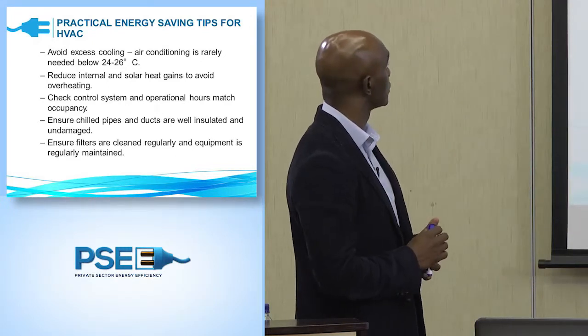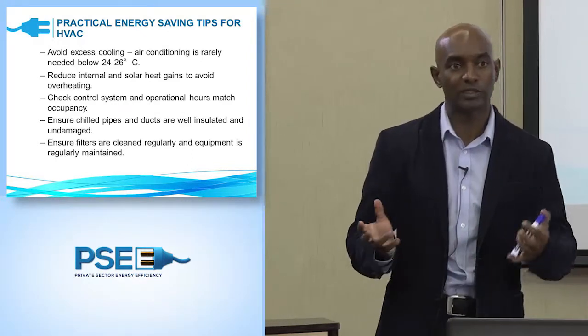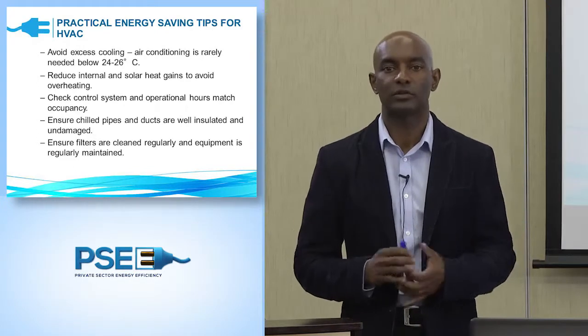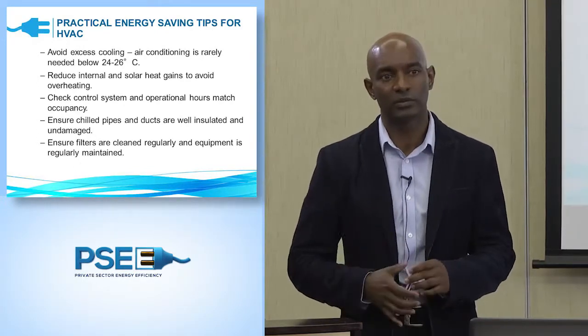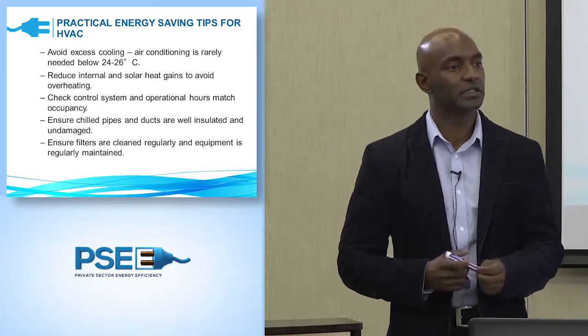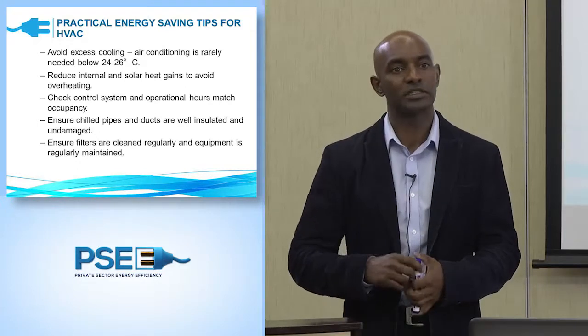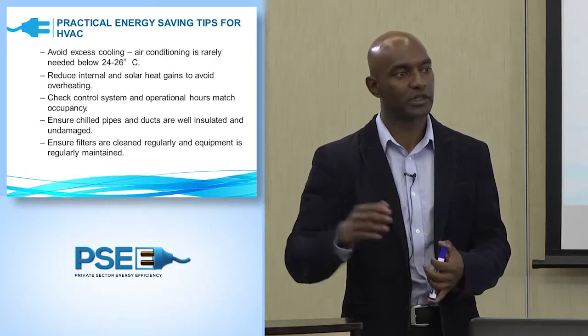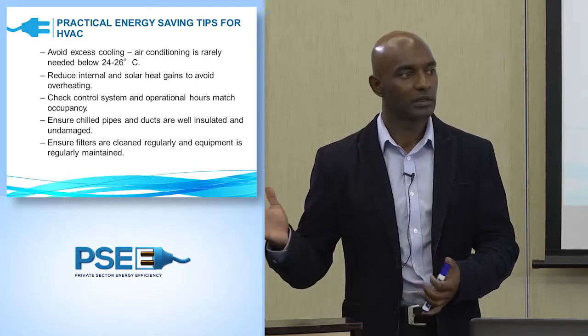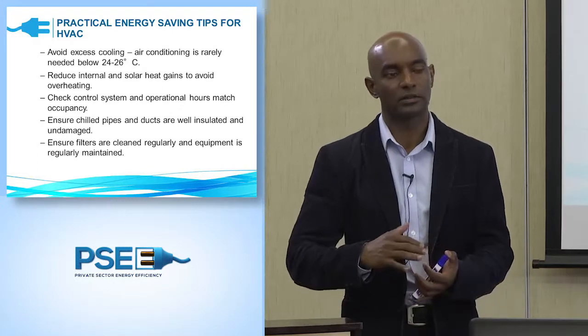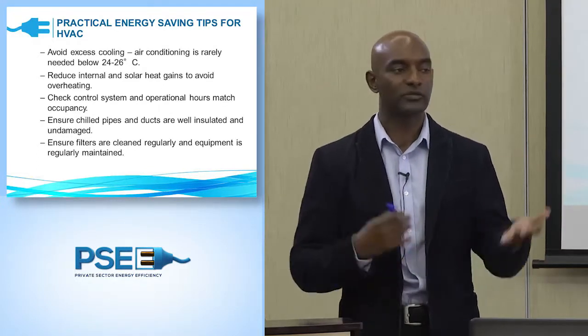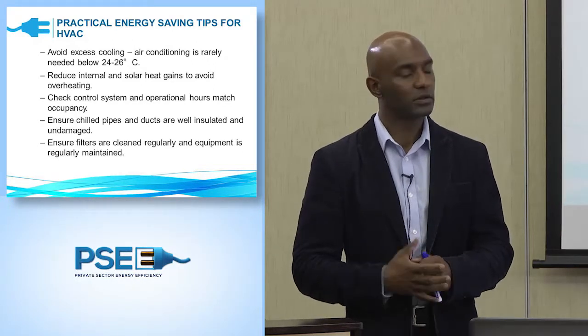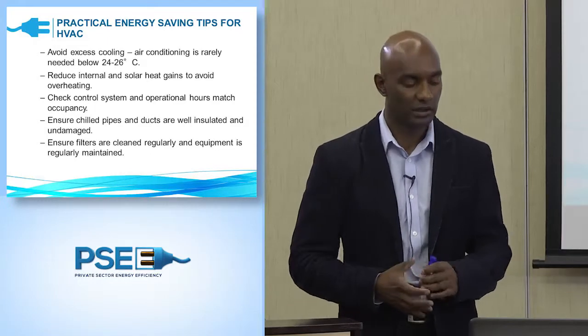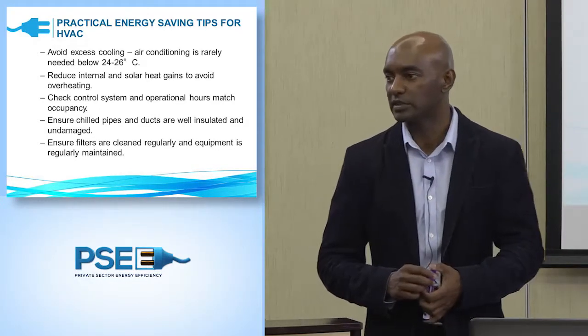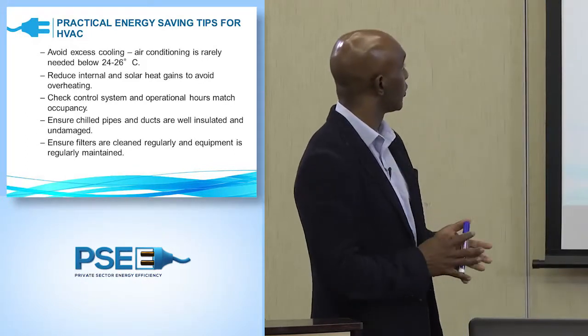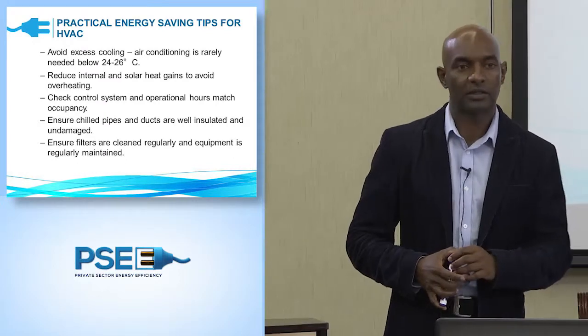Another thing is putting control systems on air conditioning to match occupancy. Systems now come with occupancy sensors or timers you can add. One project we did at UJ was installing a control system on the air conditioning for students, because when the lecture hall is empty the room still needs to be at a certain temperature since you can't switch off the aircon entirely. When the lecture starts and 100 students come in, the temperature rises quickly, so the aircon has to run. You control it like that to save energy, using building management systems (BMS) for different applications. It's also important to ensure chilled water pipes and ducts are well insulated and not damaged.